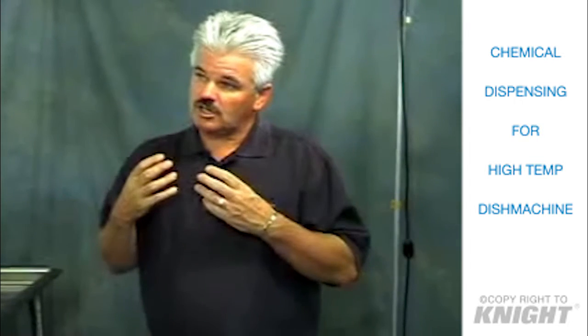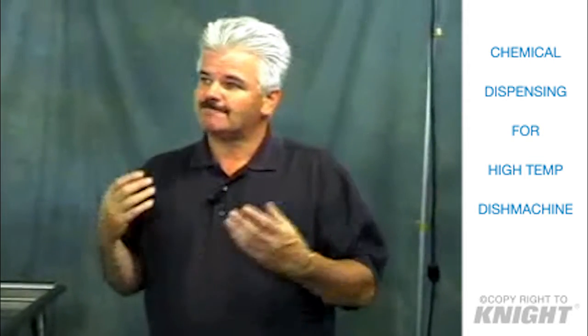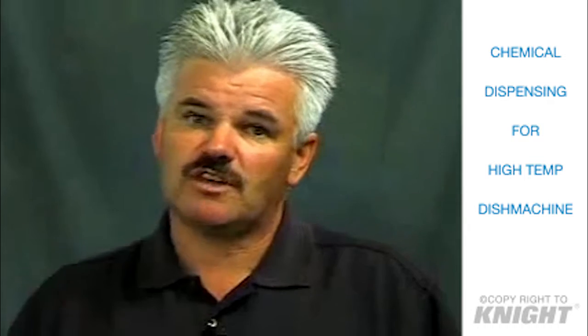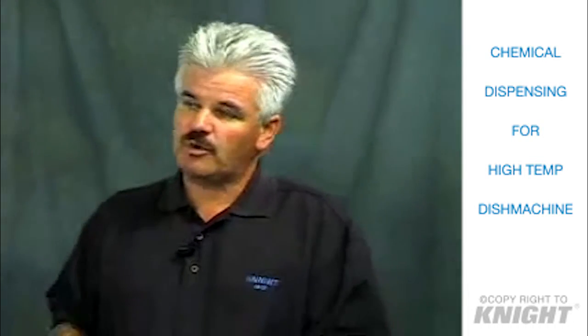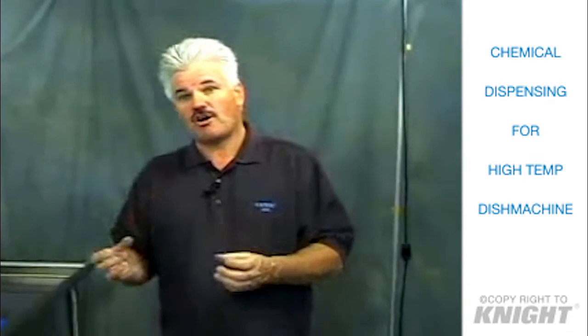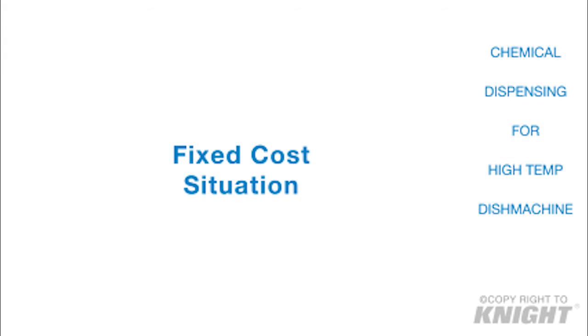So it's a great option, and it's a great selling point as well, to be able to go to the customer and say, you've been running in probe mode, and I know you're having a lot of problems with fouling probes, and somebody's constantly coming out here to clean them, so you're overusing product tremendously. But if I set you up in probeless mode, you're probably going to be able to save that customer a lot of money. So there's a lot of benefits, and the more you understand about what you can do with these controls, the more confidently you'll be able to sell your products in the field and hopefully make more money for you and your company.